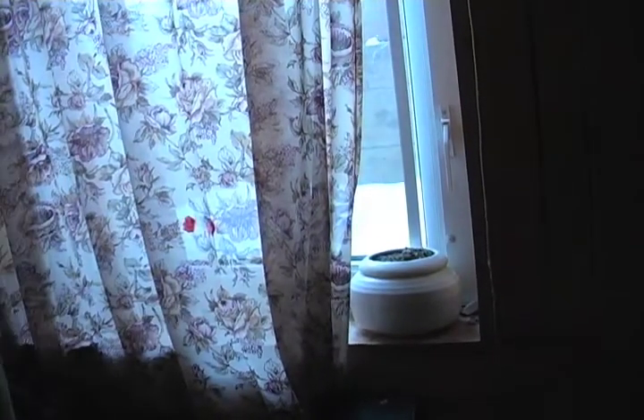Good window. Poor ceiling sealed job. And the presence of mold. You see where that cool surface is creating a place for moisture and condensing, so that black mold is growing there. Again, not a good thing.